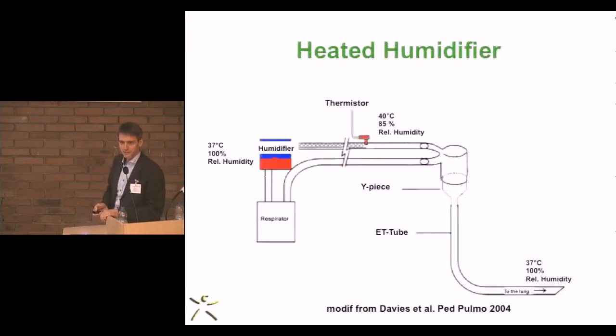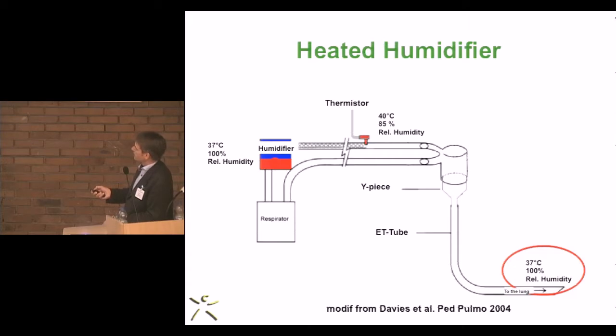Now, Davies, not Peter Davis, have been looking into the efficacy of heated humidifiers, and they have measured temperatures and humidification down the ventilator tubing system into the endotracheal tube down to the tip of the tube. And actually what they found is that when you use a heated humidifier with a heating wire in the inspiratory limb close to the Y-piece, after this heating wire, the temperature should be set up to 40 degrees Celsius because only by this adjustment, and now you have a relative humidity of 85, you are able to actually reach 37 degrees, 100% relative humidity in the endotracheal tube in the patient.